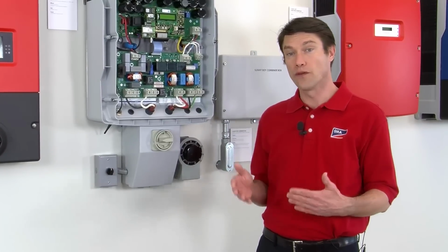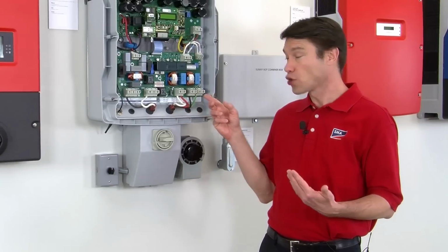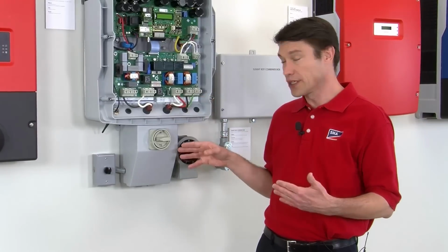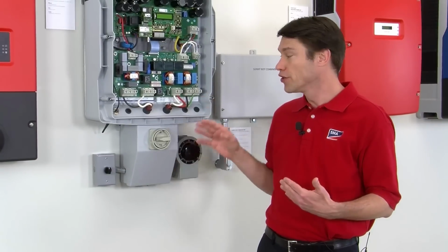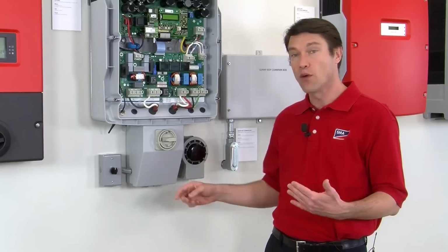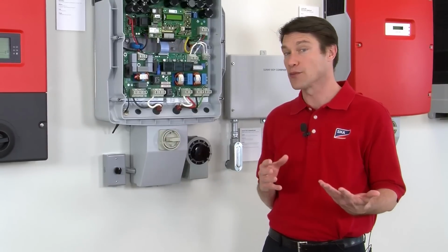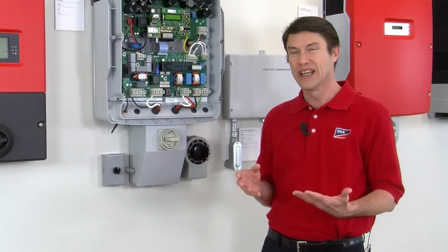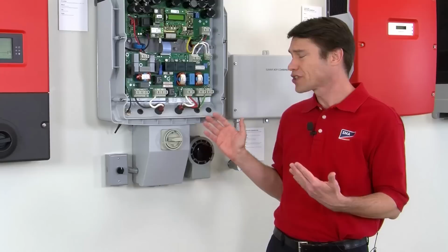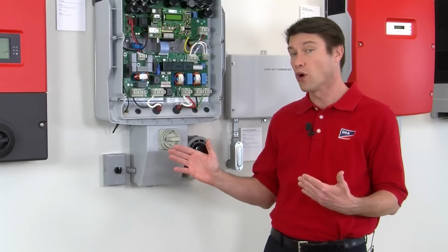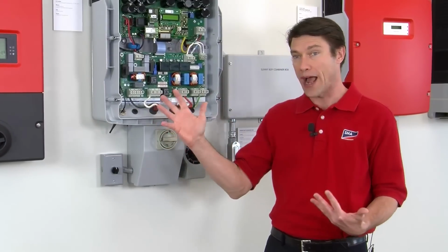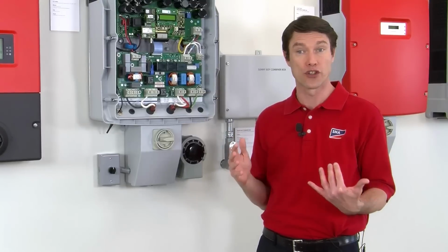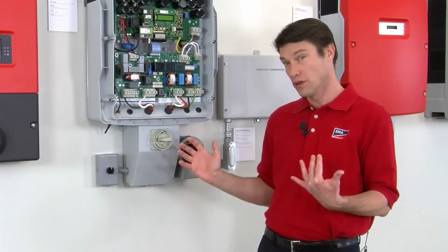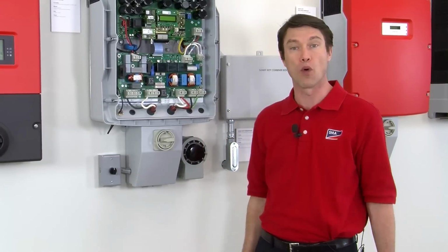Now, in the manual for the inverters we talk about the proper torques for these terminals and also for the disconnect, the proper torque for those connections. So you have that as a reference. And then anywhere else along the path that might be the possible culprit, tighten down those wires. And you can use a multimeter to diagnose kind of what connection is the problem one. Just check the terminals from the inverter back to the utility and see if there is a big voltage jump or drop, you know, at each segment, and then tighten down the culprit wires.